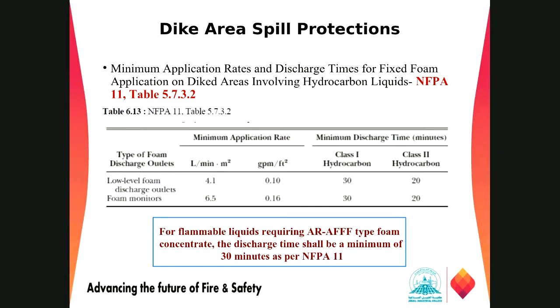Where we need to fight flammable liquid fires requiring alcohol-resistant aqueous film forming foam type concentrate, the discharge time shall be a minimum of 30 minutes as per NFPA 11. We cannot go below 30 minutes in the case of AR-AFFF foams.